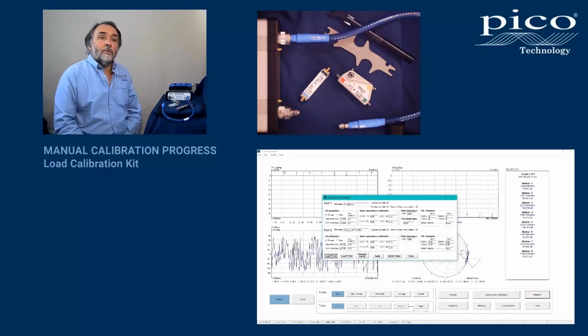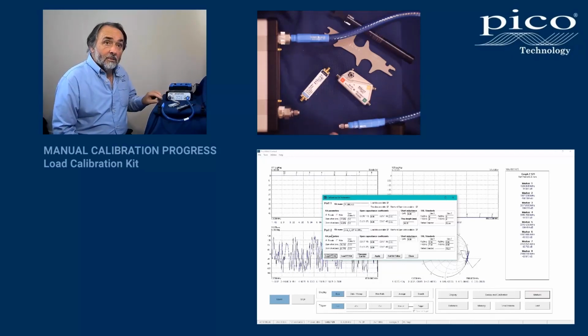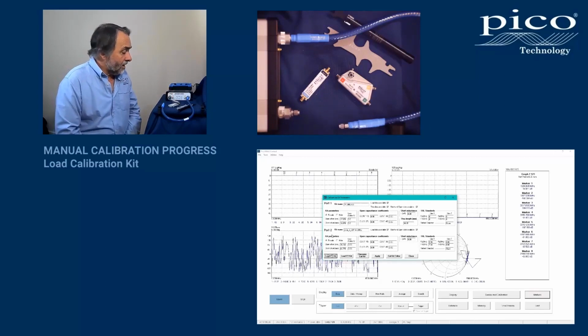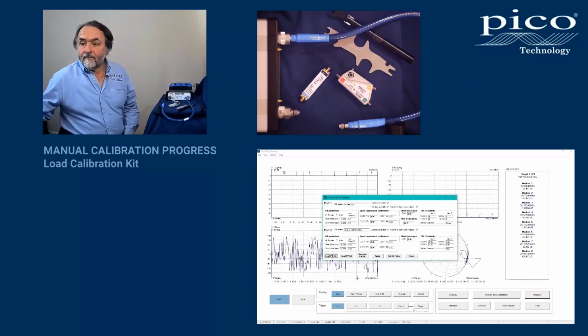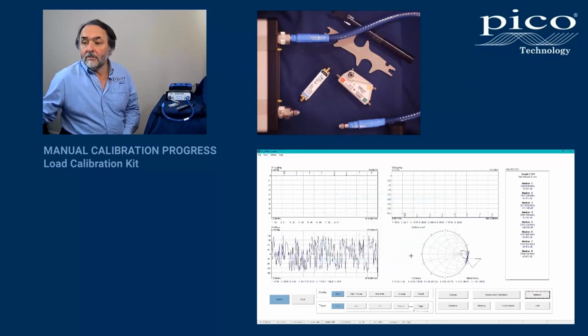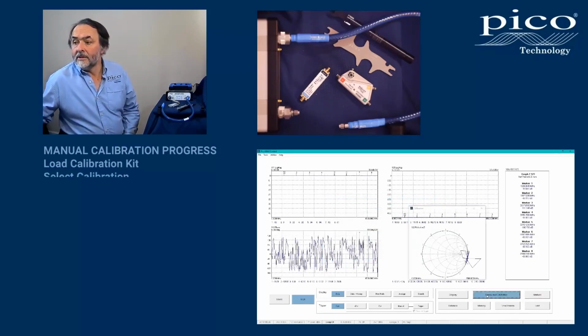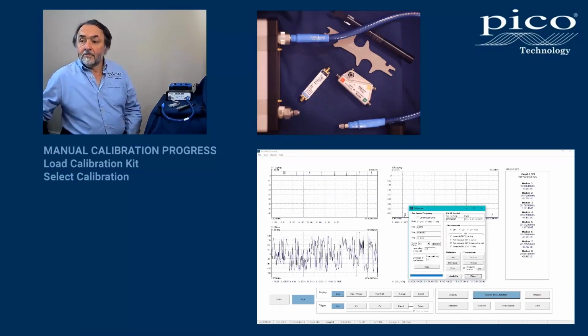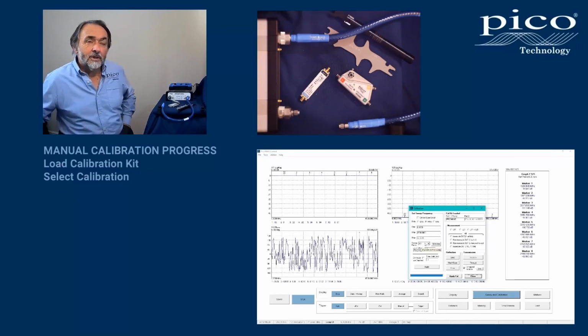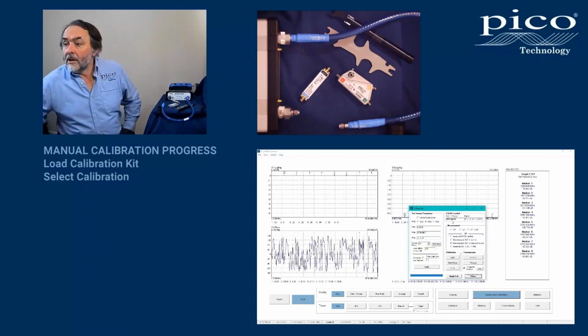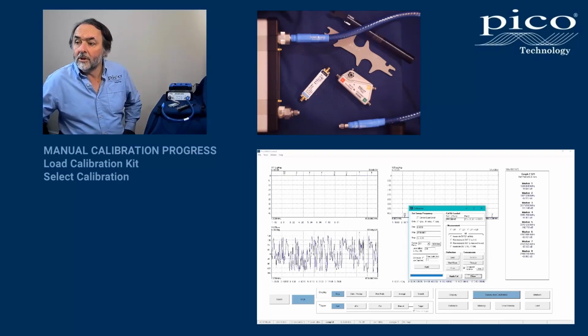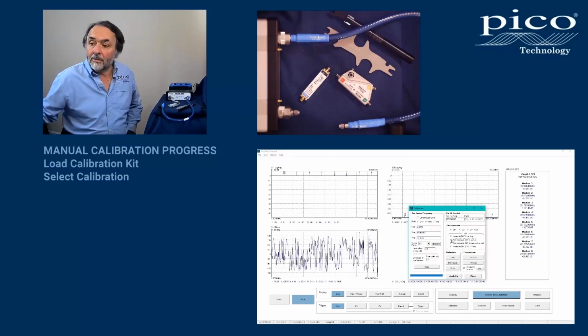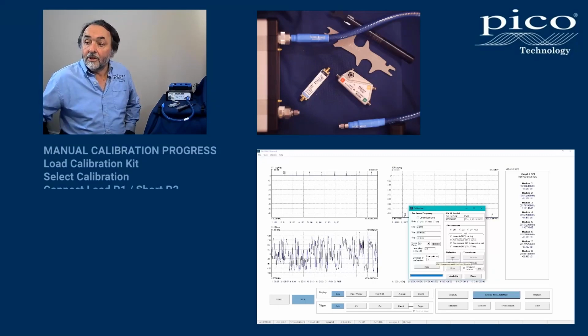I only need to load that to port 1 because I'm doing a non-insertable calibration using just one calibration standard here. Okay, apply, close. So my setup is a full span sweep. I'm using 201 points. My IF bandwidth I'm using today is 100 Hertz. And we check that the correct cal is loaded, the correct kit is loaded to port 1 and port 2. We're going to do a non-insertable calibration with one calibration kit, and I begin with the load.